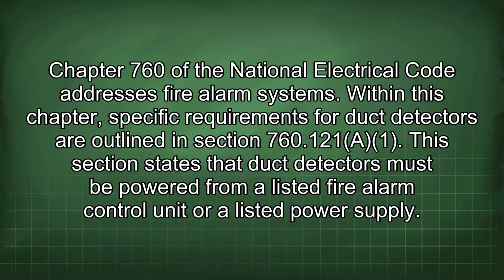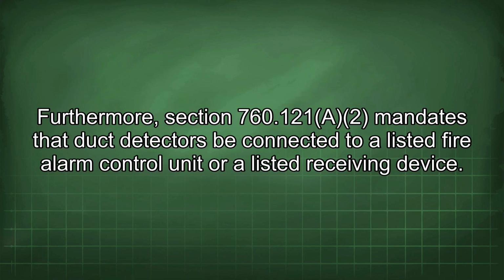Chapter 760 of the National Electrical Code addresses fire alarm systems. Within this chapter, specific requirements for duct detectors are outlined in Section 760.121(A)(1). This section states that duct detectors must be powered from a listed fire alarm control unit or a listed power supply. Furthermore, Section 760.121(A)(2) mandates that duct detectors be connected to a listed fire alarm control unit or a listed receiving device.